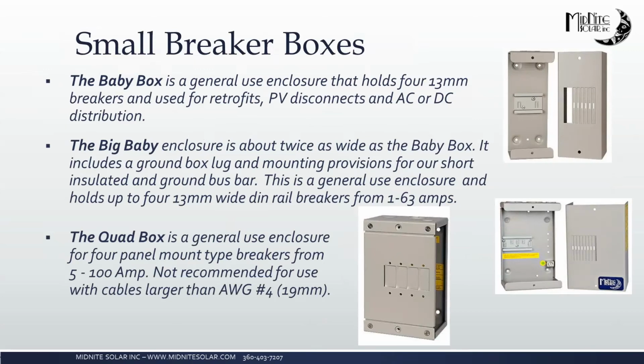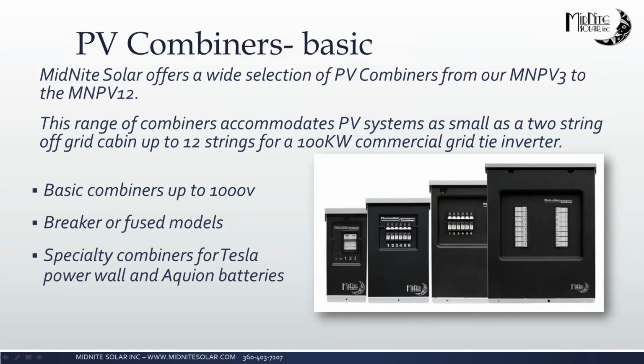PV combiners. We offer a full line. Oops. Sorry about that. There they are. No worries. From the PV3 all the way up to the PV12. So this accommodates PV systems as small as 2 strings all the way up through 12, which can handle up to about a 100 kilowatt commercial grid-tied inverter. So it does offer you a lot of flexibility there in the size of system that you want to design. The basic combiners go up to 1,000 volts, and we have breaker or fused models depending on the voltage needs that you have. We also make specialty combiners for the Tesla Powerwall and the Aquion batteries.